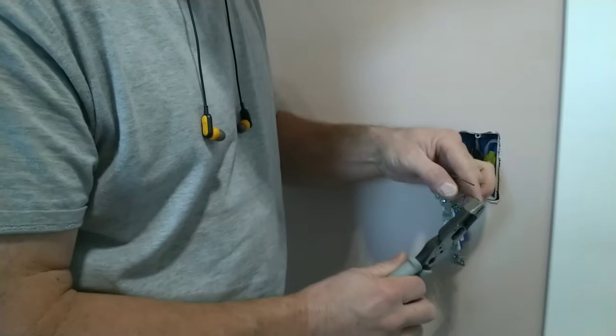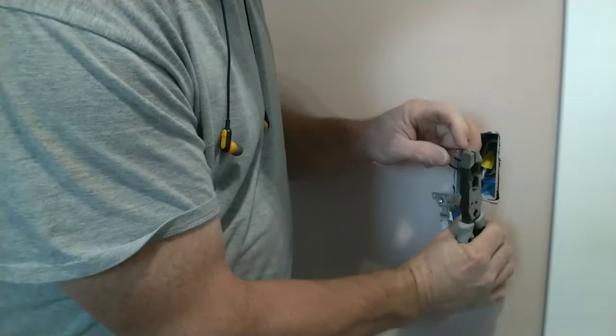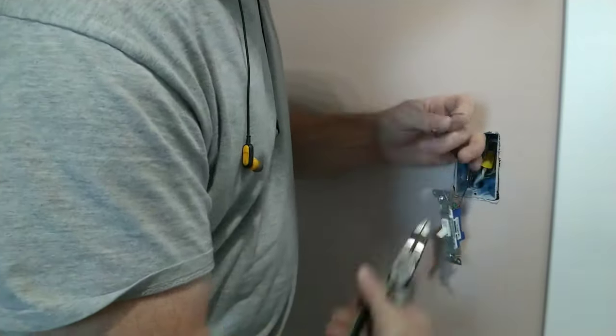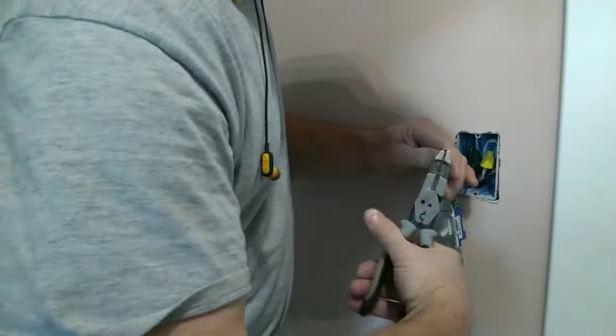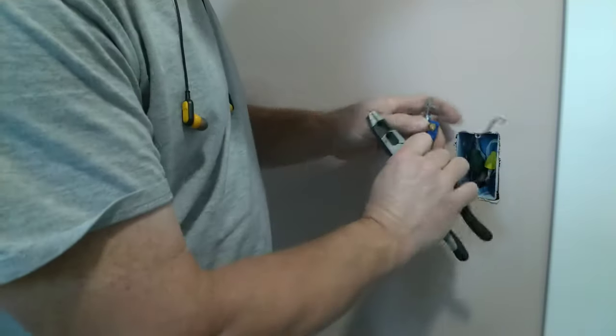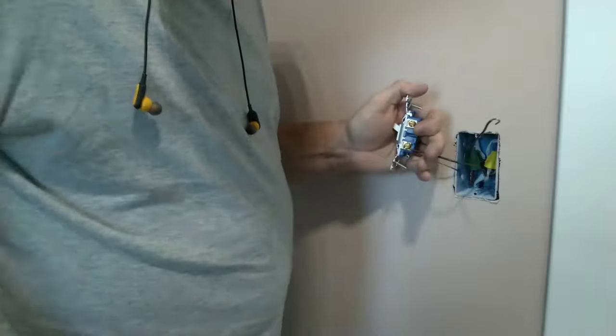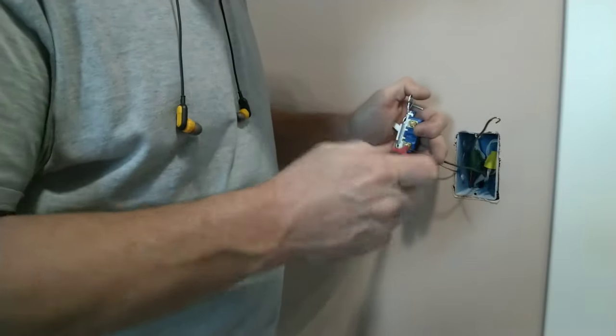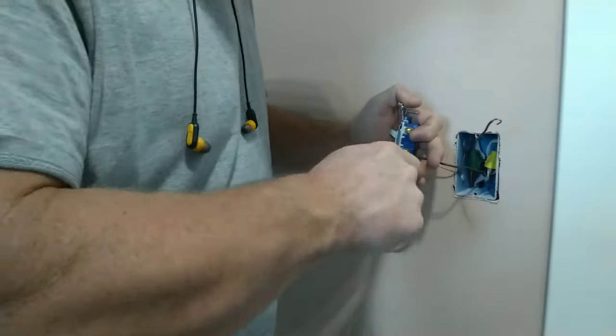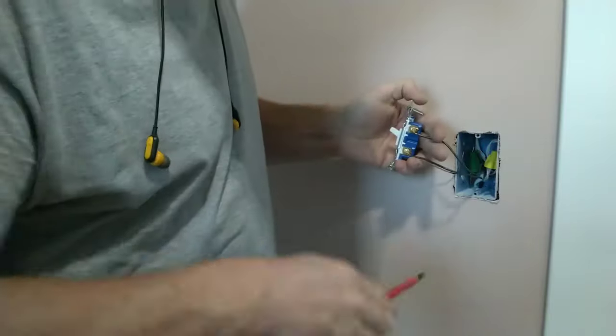I strip 1 inch on my screw terminals for switches. I'm binding the last 3/8 of an inch, and I'm spinning. Same thing on this, 3/8 and spinning. Turn your switch right side up. That's the hot leg, put the hot leg on. Tighten it up. This is your closet light hot leg.